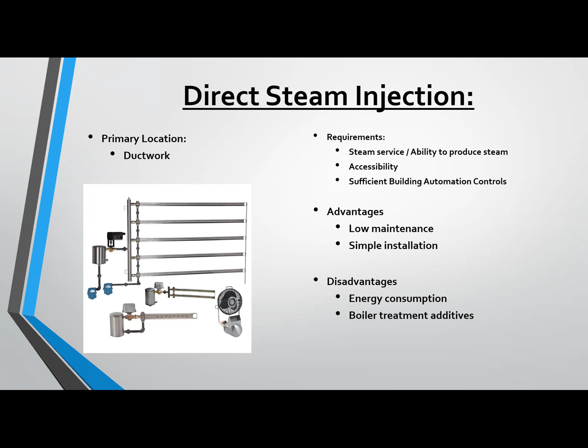Facilities are starting to see that their employees' health and well-being probably far outweighs a little bump in the utility bill. Another disadvantage to this is you really need to make sure your boiler treatment additives are compatible with the materials these are made out of, and that those additives are applied in the right dosage. You can go both ways, too much or not enough. It's really important to be right on the money with that.